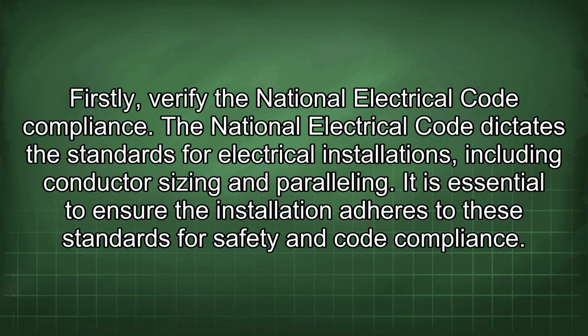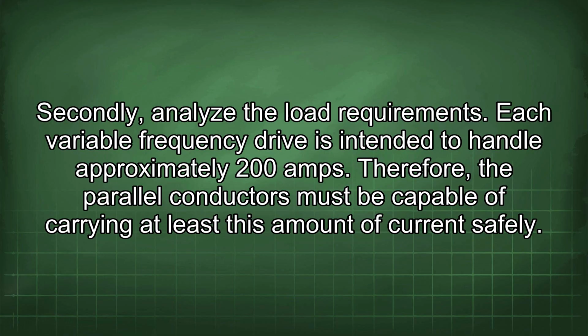The National Electrical Code dictates the standards for electrical installations, including conductor sizing and paralleling. It is essential to ensure the installation adheres to these standards for safety and code compliance. Secondly, analyze the load requirements. Each variable frequency drive is intended to handle approximately 200 amps. Therefore, the parallel conductors must be capable of carrying at least this amount of current safely.